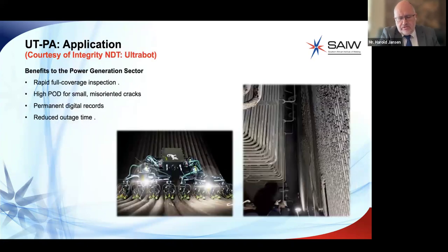Some of the benefits to the power generation sector with regards to ultrasonic inspection of small bore boiler tubes are the rapid full coverage inspection, the high probability of detection for small misoriented cracks, the permanent digital records for risk-based inspection programs, as well as the reduced outage time compared to manual UT point measurement or RT film processing. Integrity NDT employs an ultrabot, which is shown in this central picture, to conduct remote inspections in areas that are challenging to access, thereby eliminating the need for scaffolding.